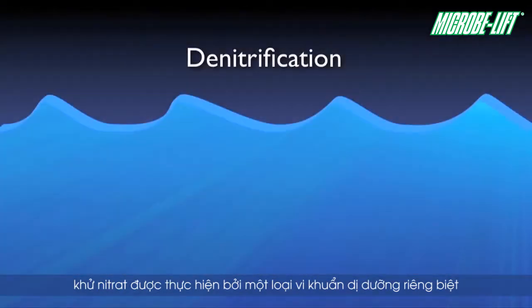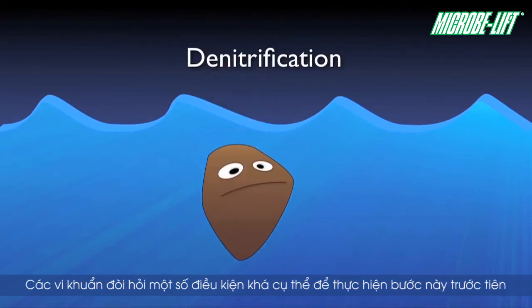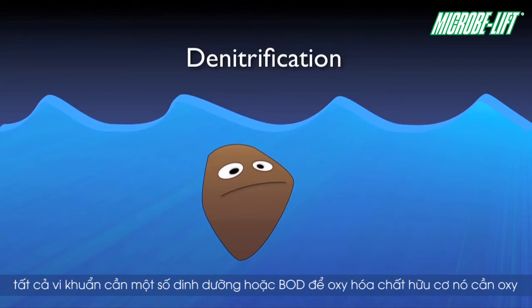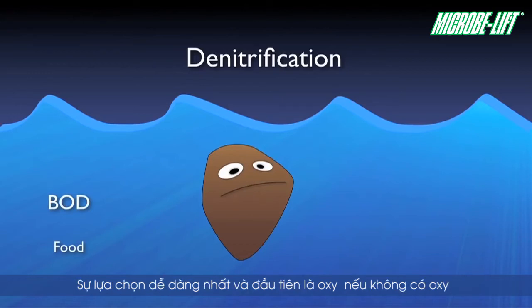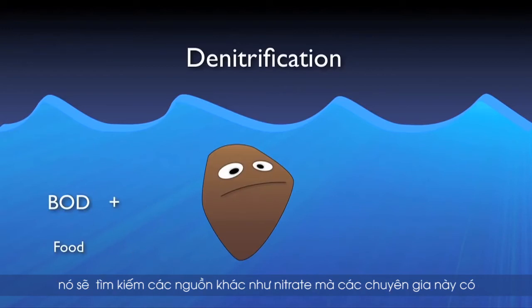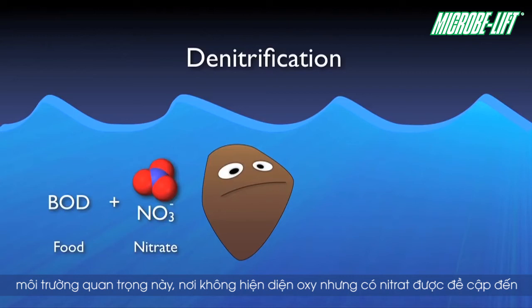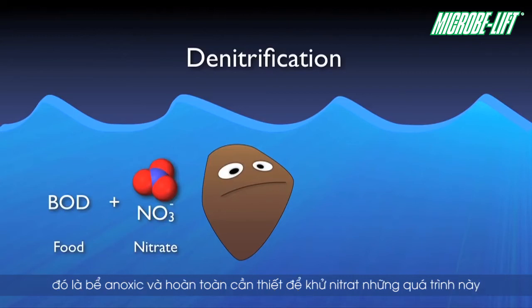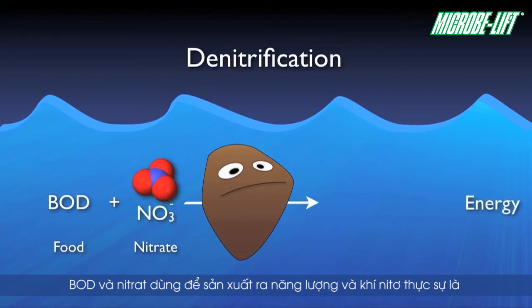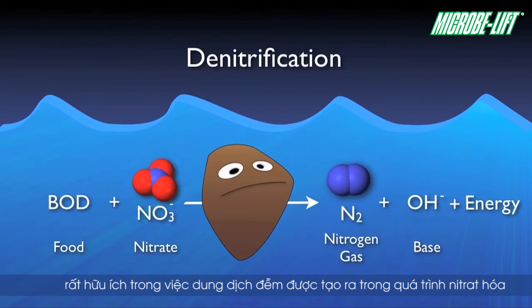Denitrification is performed by specialized heterotrophic bacteria. These organisms require specific conditions: they need some food, or BOD. In order to oxidize that food, they need oxygen. Their first choice is dissolved oxygen. If there is no DO present, however, they look to alternative sources such as nitrate. These specialists have the ability to strip the oxygen from nitrate molecules to satisfy their needs. This critical environment where DO is not present yet nitrates are is referred to as anoxic, and is absolutely required for denitrification. These bugs take the BOD and nitrate to produce energy, base, and nitrogen gas. The base is actually very useful in buffering the acid produced during nitrification.